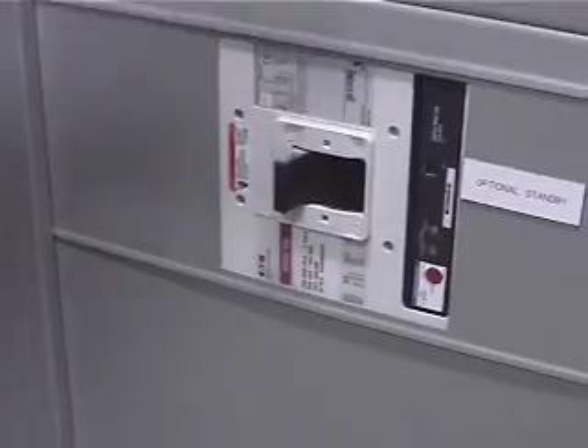But like you say, quick scenario: power goes out, generator starts, nothing else happens. You go out there, you check that breaker - it's on. Okay, the next thing I'm going to look at is this emergency distribution panel, right here, one of these breakers. Each one of these breakers in this panel runs 1 transfer switch. So that's the next thing I'm going to look at.